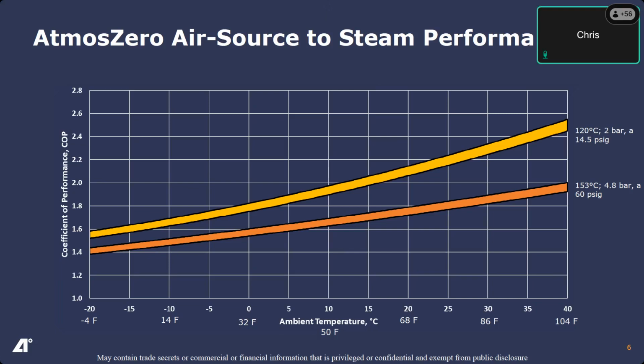What else? Maybe one last comment here is, a lot of times people say, okay, so what happens if it gets too cold? So you can see on the top bar there is Celsius, the bottom bar is Fahrenheit on the temperatures. If you get below -20°C or -4°F, what happens is your COP starts to come down pretty quick, and we basically turn into a resistance boiler. So the low cycle of the heat pump stops sourcing heat from the air, and we run that cycle and recycle, which then heats the top side, which then still makes steam. So it's not an issue of will it work, it's just an issue of efficiency. And so in those very cold temperatures, we look at that as part of the analysis that I mentioned to see how many hours a year we're going to be operating in those cases, and we can make decisions accordingly.